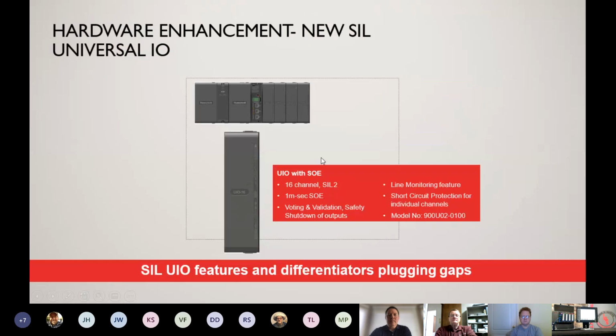One of the other I/O modules that is a big differentiator and will help save some cost and spare parts out on the plant floor is an enhanced universal I/O module, where you can program analog in and analog out on one board. It comes with 16 channels and a 1 millisecond scan, which is very fast in the industry. And then you can do things like a line monitoring feature, where you can actually monitor the input and output and have some advanced diagnostics to help you in troubleshooting the system if you need that.